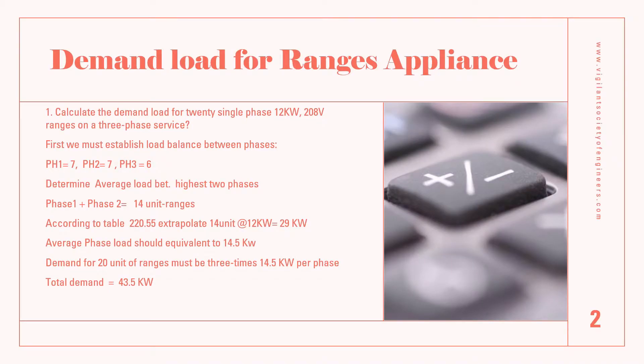We're going to calculate the demand for 20 single-phase 12 kilowatt, 208-volt ranges on a three-phase service. For a question like this, we should establish a balance basis. We have 20 units and we're going to spread them evenly between phase one, two, and three — so phase one gets seven units, phase two gets seven, and phase three gets six.